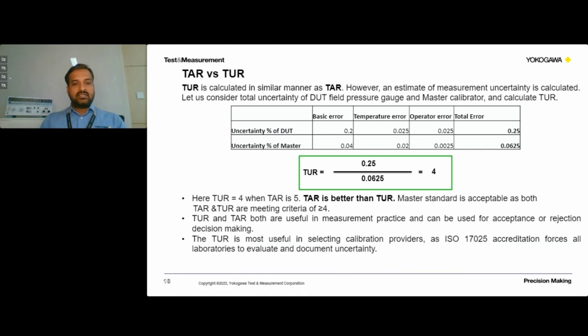And test uncertainty ratio is most useful in selecting calibration providers. So when we send any instrument for calibration to any lab, we can check what their uncertainties are, how the uncertainties are checked in their calibration lab, and we can have a sample calibration certificate from them. To choose the better calibration providers, we can use test uncertainty ratio. Because ISO 17025 mandates that all the calibration labs should document and evaluate the uncertainties existing in their labs.